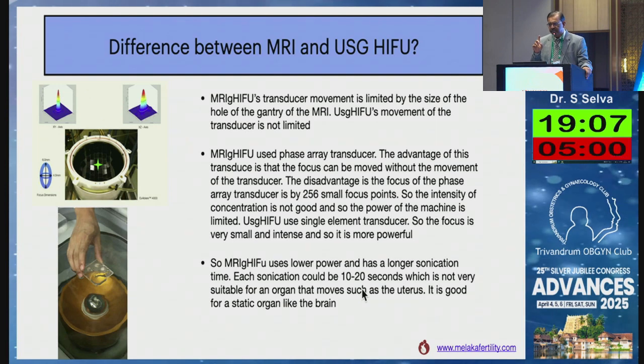This is very important because if you're doing the brain, it's okay, you can fix the brain and you can wait for 20 seconds. Whereas if you're doing a uterus, the patient can move, and that will affect it. So your positioning of the beam cannot be nearer to the serosa or the endometrium, as opposed to ultrasound-based HIFU, where we can go very close to serosa and endometrium because we are doing it second by second. It is done under live ultrasound. So that is the difference.